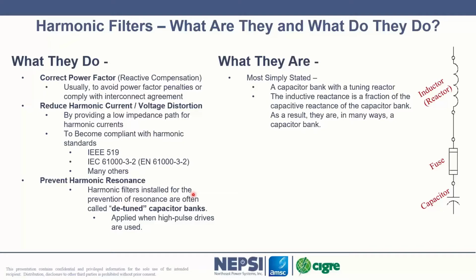And then finally, the third reason is that you need to filter the harmonics. You're trying to meet an IEEE standard or an Australian standard for distortion, or maybe it's a local utility standard. You're trying to meet that standard either for voltage distortion or current distortion, and a filter provides a low impedance path for harmonic current, and also helps to reduce voltage because of that low impedance path. So that's the third reason.